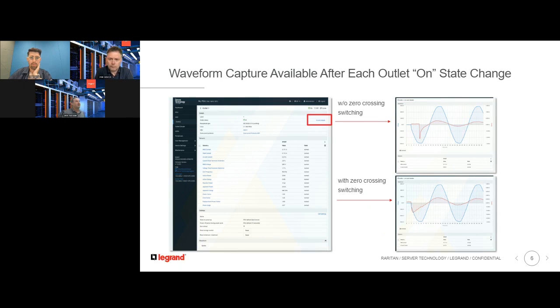So if we look at the waveform capture, this slide actually covers a couple different things. One is that as relays are turned on, and you're looking at things like current inrush, we also have a feature within our products where we want to make sure that when the relays are turned on, we maximize the life of those relays. And a fairly unique feature that I believe we've patented is that we will switch on the relays at the zero crossing, and that really limits the amount of power that the relays are seeing. It extends their life. It also makes it easier on all the components within the PDU itself. So we actually will do our switching at zero crossing, and we will also look at the current inrush as the PDU is started up and the relays are switched on.